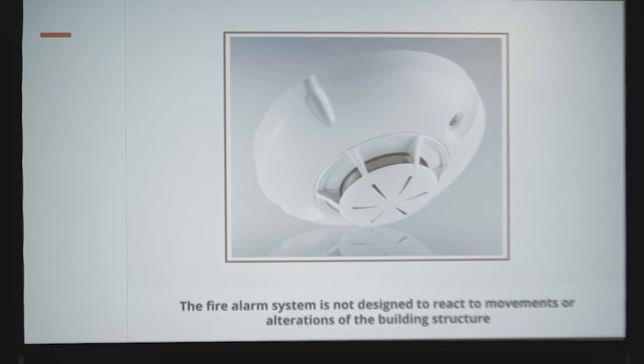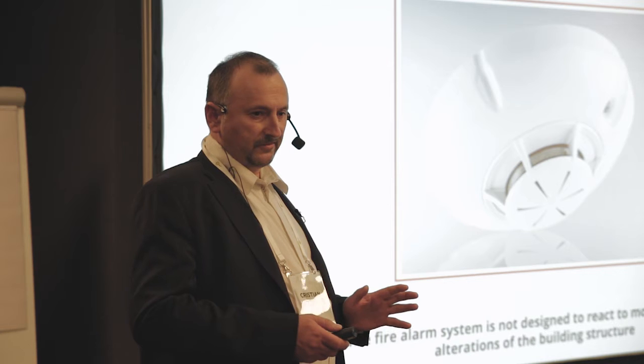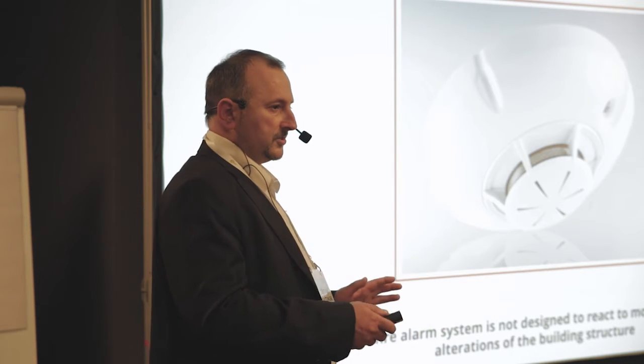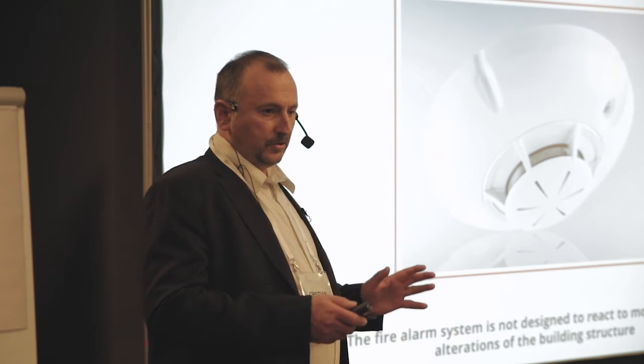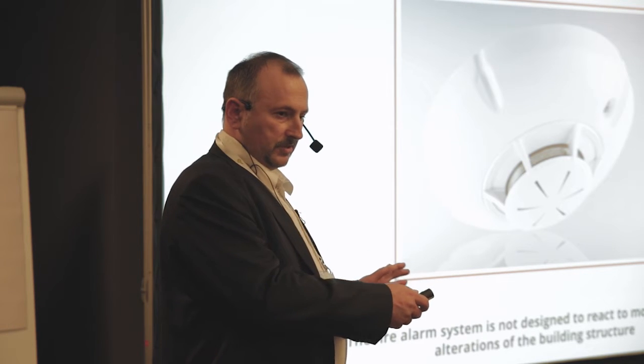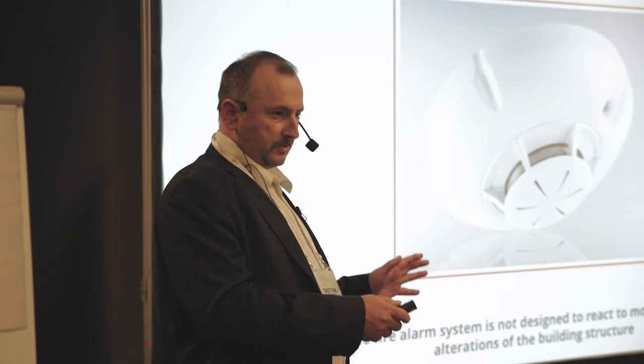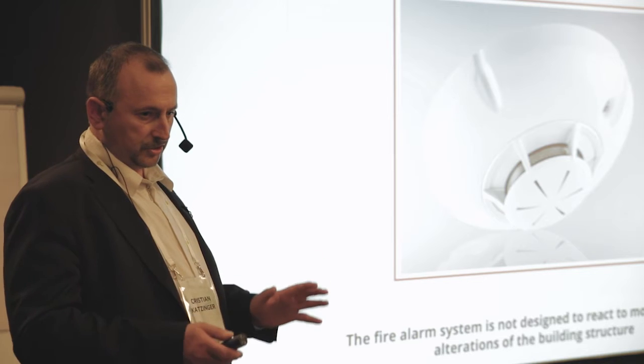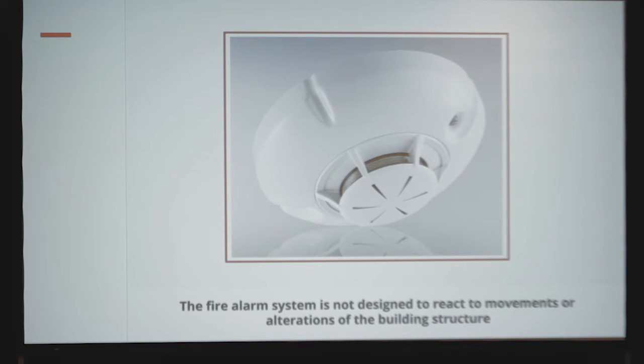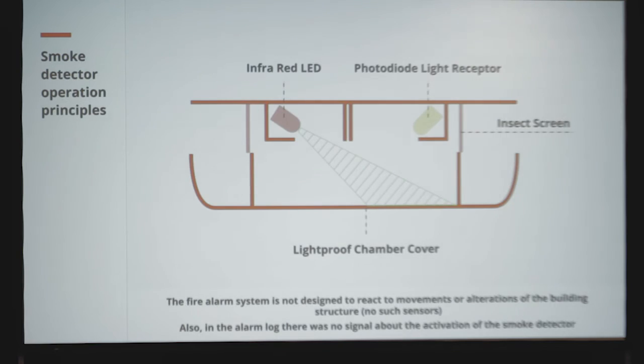What's happening inside? If there's a loose contact or a break of wires, it wouldn't cause any fire alarm; it would just send a failure to the control unit. Look, there's a mistake, please check it, change it, but not a fire alarm. A fire alarm from such smoke detectors is only caused in one way.